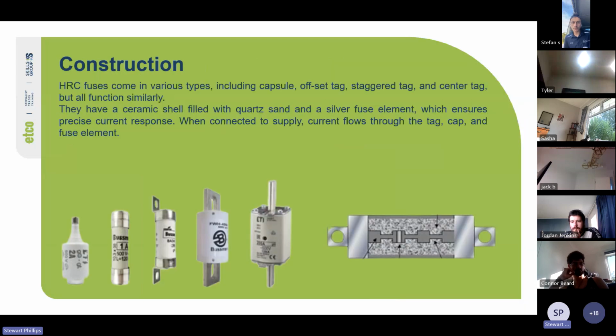Yep, cool. So construction. HRC fuses come in various types, including capsule, offset tag, staggered tag, and center tag, but all function similarly. So those are the different types there. You've got your two capsule fuses there, your offset tag and your staggered tag, and then the center tag there. They have a ceramic shell filled with quartz sand and a silver fuse element, which ensures precise current response. When connected to supply, current flows through the tag, cap, and fuse element.